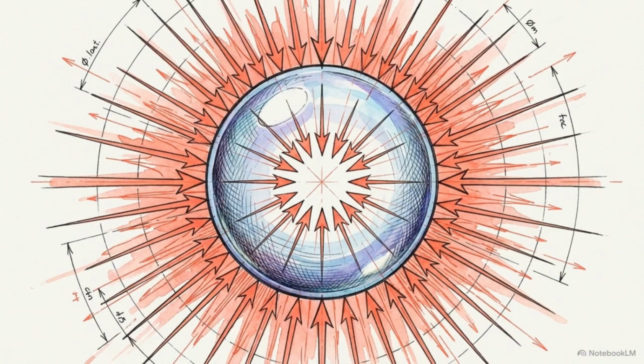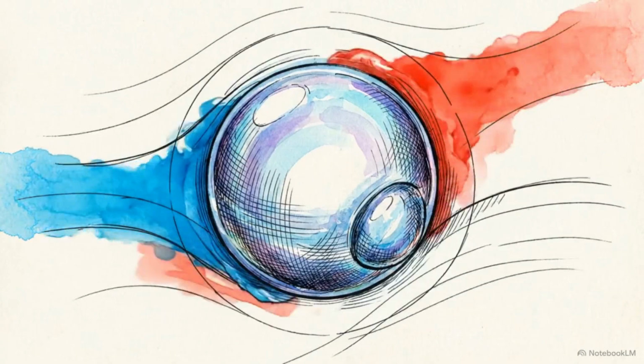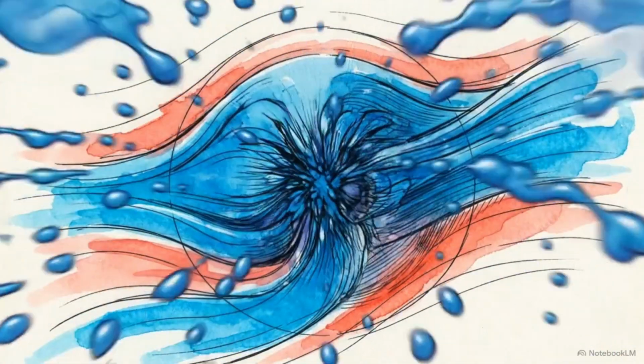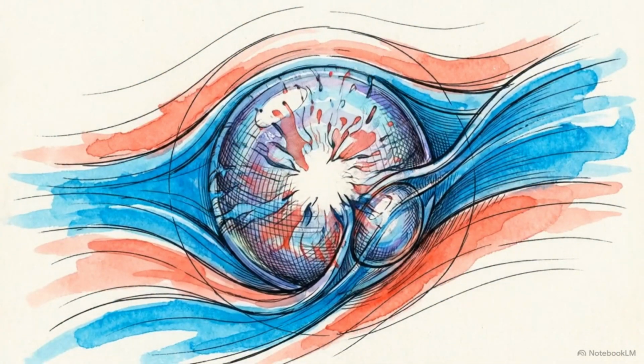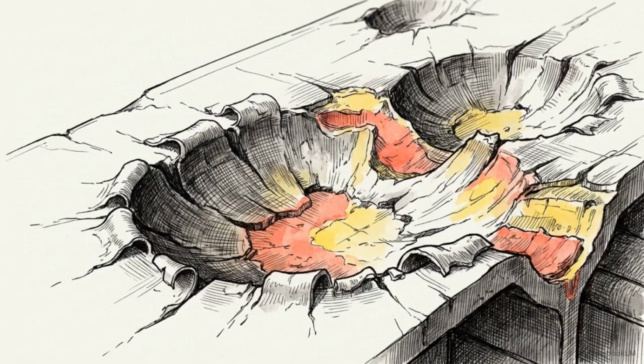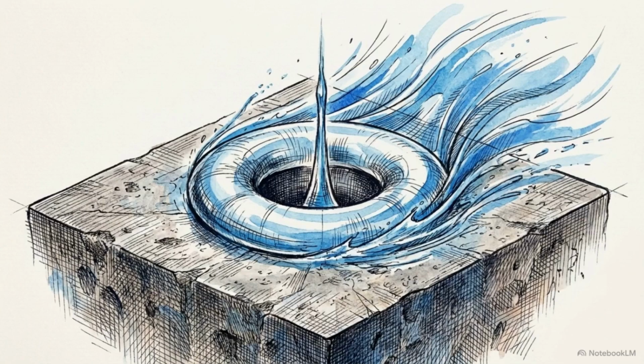When the bubble eventually leaves the low-pressure zone, the surrounding pressure recovers. The massive inertia of the surrounding liquid accelerates inward, converging on the void. Because a solid wall blocks the liquid, the collapse is uneven. The bubble's far side caves inward, piercing the cavity to form a shrinking donut wrapped around a high-speed water needle. This microjet strikes the metal at extreme velocity, driving shock waves across the surface. Millions of these repeating impacts fatigue the metal until microscopic chunks tear away. This temporary geometry focuses distributed liquid momentum into a microscopic, point-like projectile.